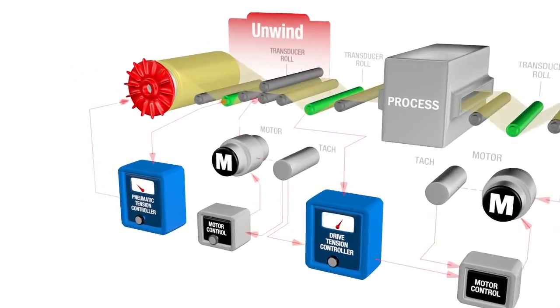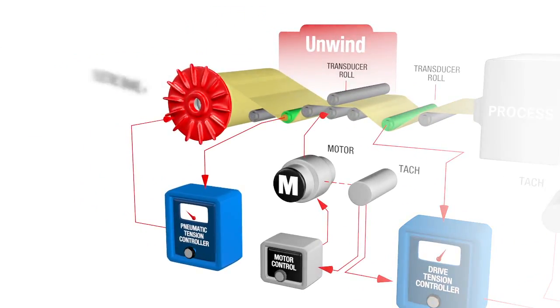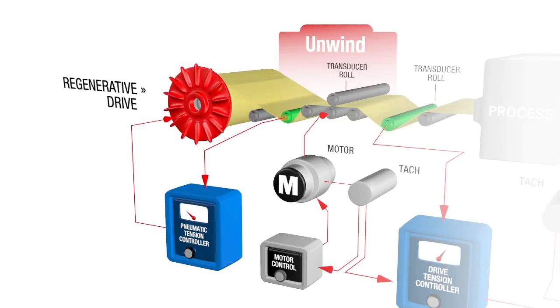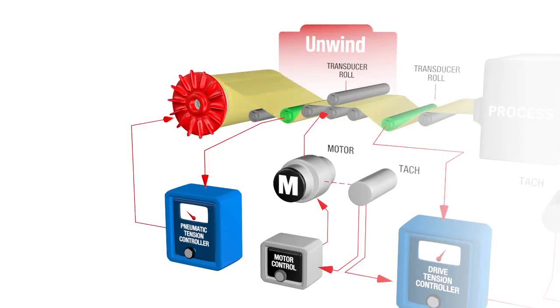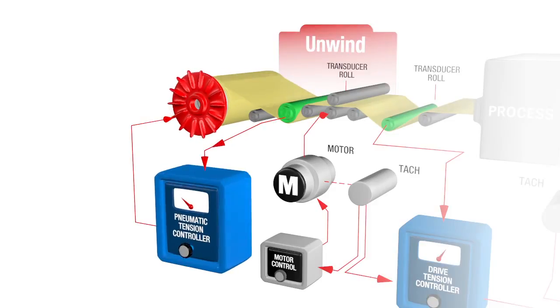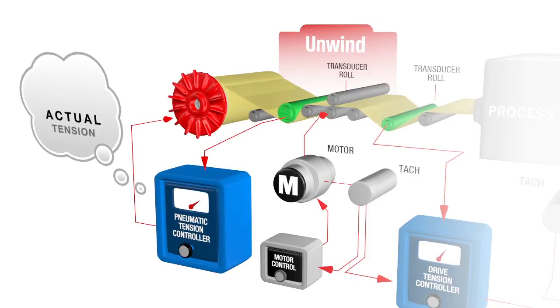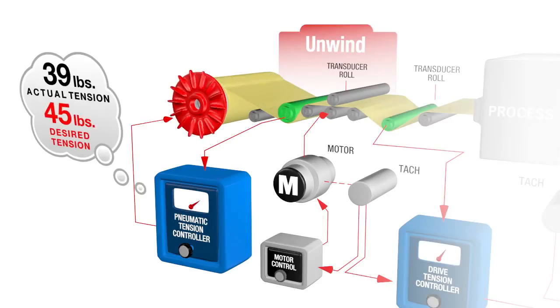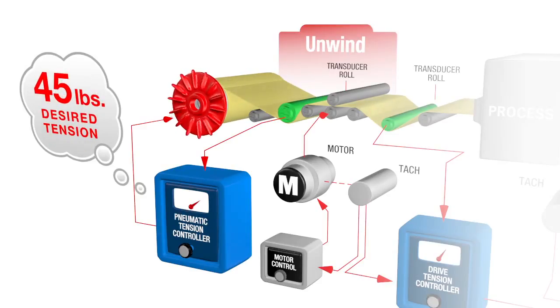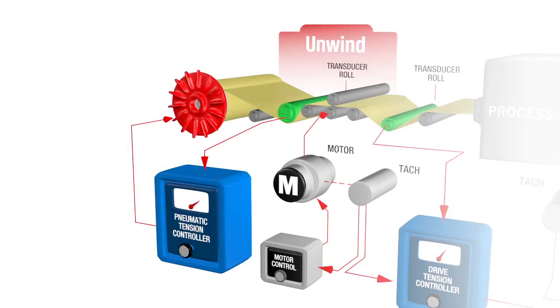Tension in the unwind zone can be controlled by a pneumatic brake, an electric brake, or a regenerative drive. During machine operation, the measurement signal from the tension transducers is input to an automatic tension controller. The controller compares the actual tension to a desired tension set point input by the operator, and sends a compensated electric or pneumatic signal output to the control device. The output signal decreases as the material roll decreases in diameter to maintain constant tension going into the next tension zone.